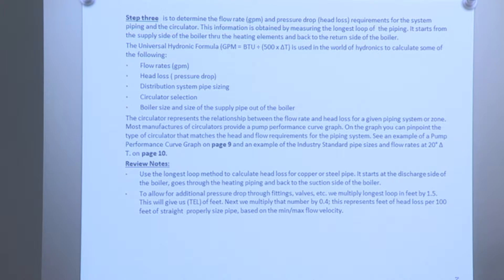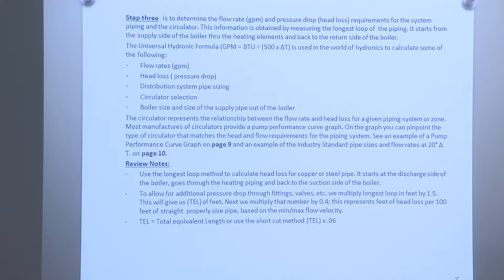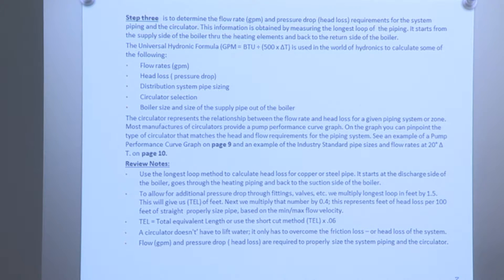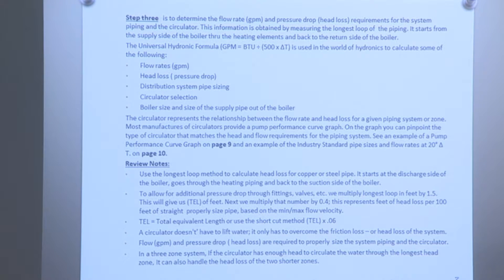Multiplying by 1.5 gives us the total equivalent feet. Next, we multiply that number by 0.4, which represents feet of head loss per 100 feet of straight pipe, properly sized based on min-max flow velocity. Using the short-cut method, you can take the total equivalent length times 0.06. A circulator doesn't have to lift water — it only has to overcome the friction loss or head loss of the system. In a three-zone system, if the circulator has enough head to circulate water through the longest zone, it can also handle the head loss of the two shorter zones.